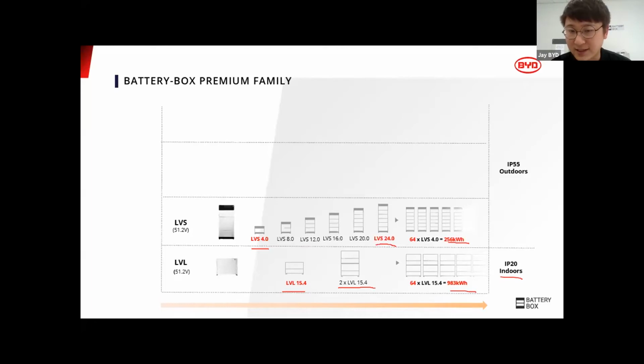I put in IP20 here just to show you the major difference. So if the customer wants a 48 volt system for off-grid, there are two major differences. Which one should you select? The first thing to consider is whether the installer needs to install the battery outside the house, because if it's outside, you need IP55 no matter what. But if it's going into a garage or storage room inside the house, then both options are okay.